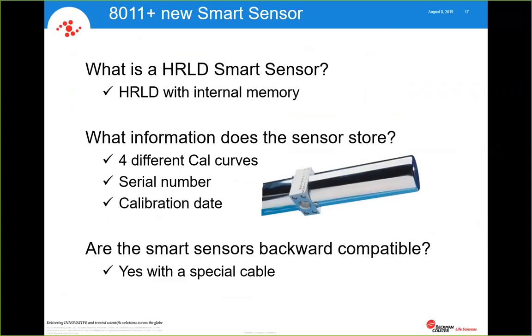Are they backwards compatible? They are backwards compatible. You just have to have the cable adapter to go back to. So if you have an 811 system and you wanted just to buy a new sensor, even though it's a smart sensor, it's still compatible with your old system. The electronics just would not allow you to upload your calibrations from the sensor to the electronics. You still have to program that in a manual mode.